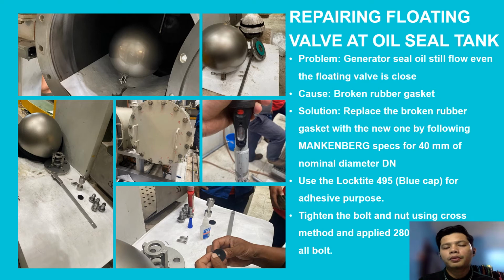Repairing the floating valve at oil seal tank. Oil seal is used to seal the hydrogen used for the generator cooling purpose. Function of the floating valve is to maintain the level of oil seal inside the tank. The problem with this valve is the oil seal still flow even the valve is in closed position. This is due to the broken rubber gasket inside the floating valve. Seal oil need to be drained first before we can fix the floating valve. After the floating valve can be accessed, we can fix the floating valve by replacing the rubber gasket.